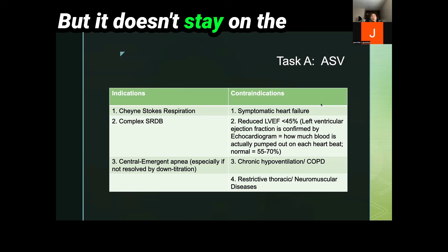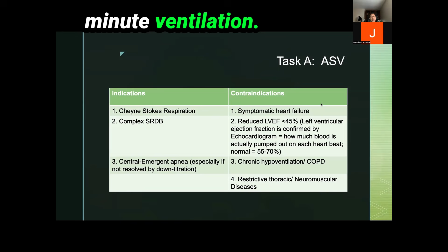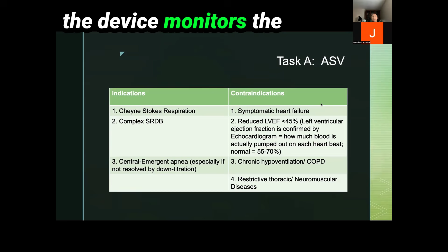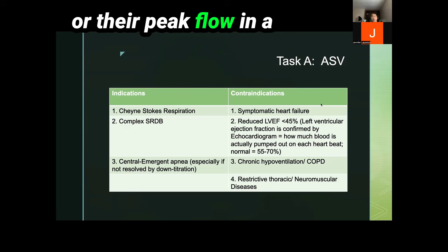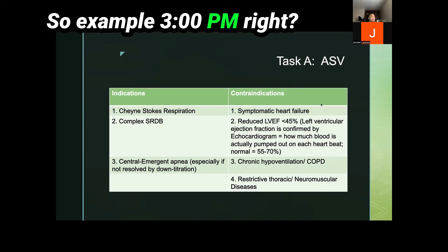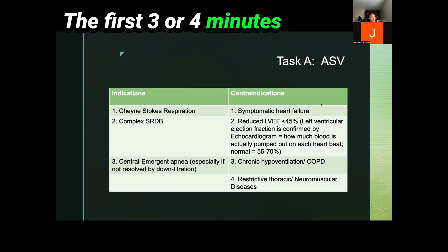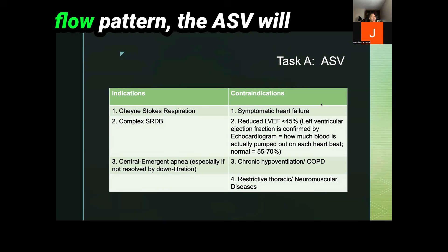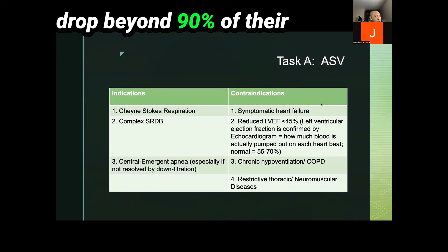But it doesn't stay on the initial target. All night long, we change our minute ventilation. So the point there is that the device monitors the patient's minute ventilation or their peak flow in a moving target, right? So for example, 3 p.m., you start the device. So the first 3 to 4 minutes, say 3:03 or 3:04, the first 3 or 4 minutes, it collects the pattern, whether it collected minute ventilation or peak flow. It already knows the patient's pattern. I will look into this patient's minute ventilation from now on and will not allow the patient to drop beyond 90% of their own minute ventilation.